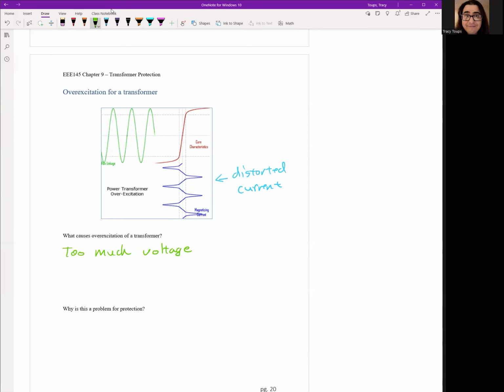Too much voltage will cause the core to enter saturation, because there are no more moments left to turn. Those little mini magnets, we ran out, and it can't hold the magnetic field anymore or make it any stronger. So all the extra voltage we're putting in after saturation, and all the extra current flowing in after saturation, is not going to get transferred to the other side. So you're going to lose your turns ratio.